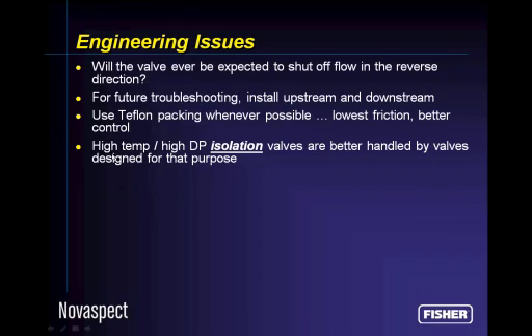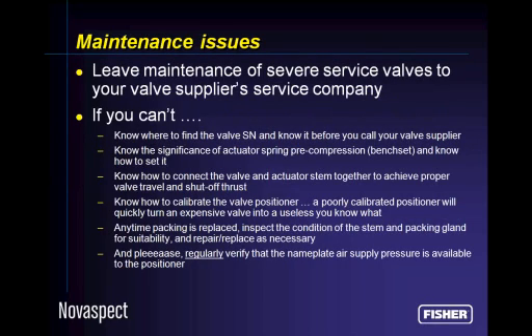And listen, if this is a high temperature process, a very high differential pressure, and you want this control valve to shut off tight, all of us valve manufacturers would prefer that you use a different valve for that. Use a valve expressly built for the purpose of isolating high temperature, high pressure drop services. Motor operated gate valve, a manual gate valve. Your very expensive severe service valve is going to last a lot longer if you do. First of all, leave maintenance of your severe service valves to your valve supplier service company. I can't stress that enough. They're really trained to take care of them appropriately.